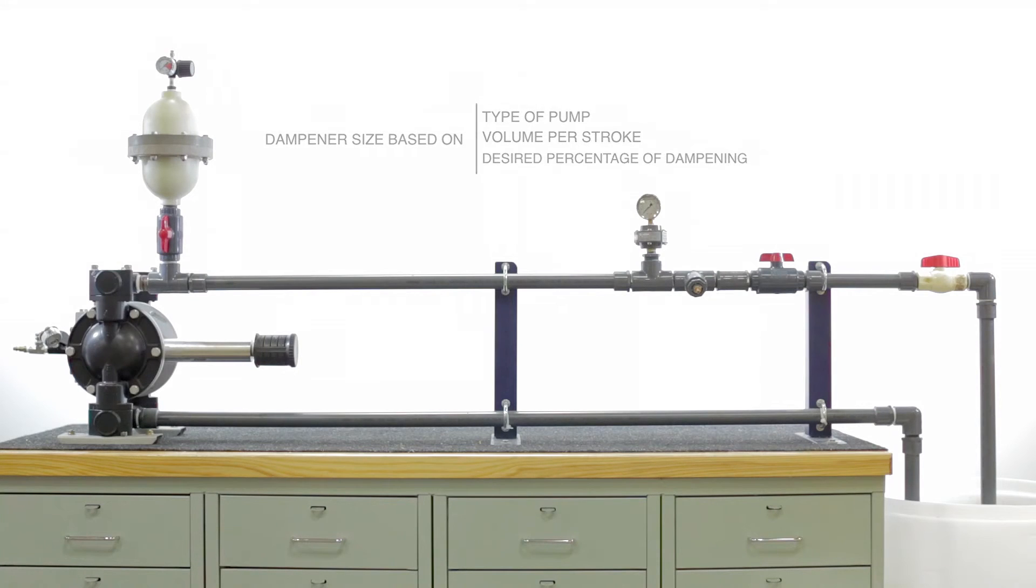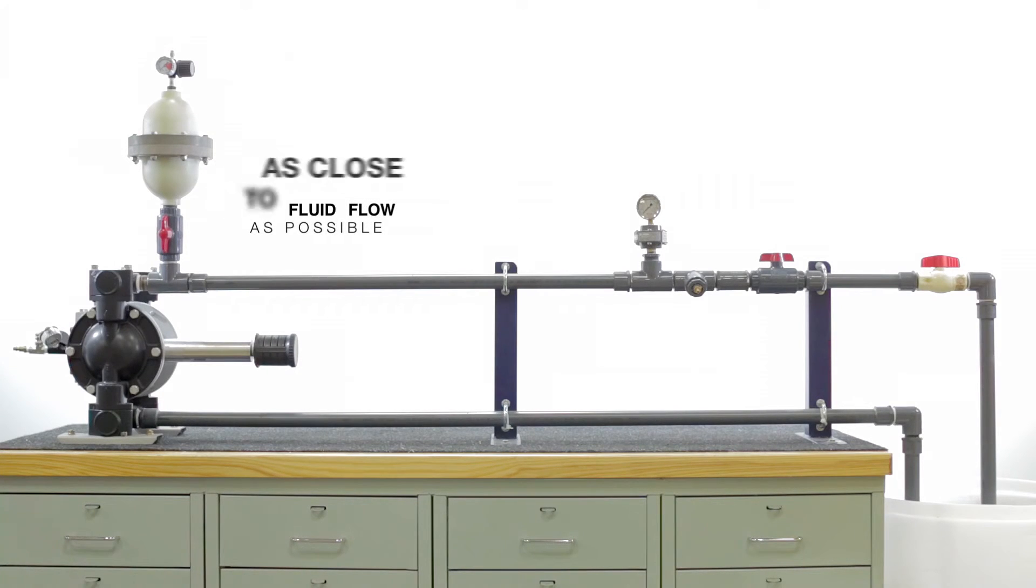Location should be as close to the pump discharge as possible within 10 pipe diameters. The dampener should not be mounted on any branches or any type of risers. You want it as close to the fluid flow as possible.